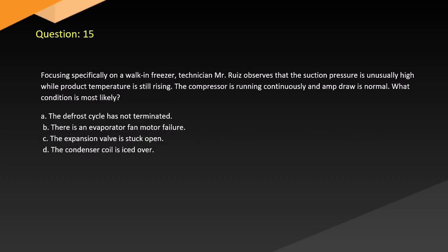Question 15. Focusing specifically on a walk-in freezer, technician Mr. Ruiz observes that the suction pressure is unusually high while product temperature is still rising. The compressor is running continuously and amp draw is normal. What condition is most likely?